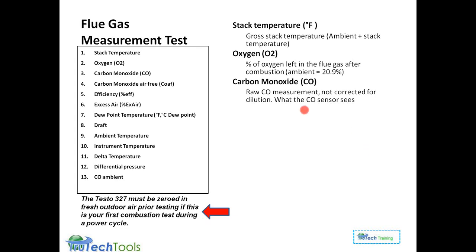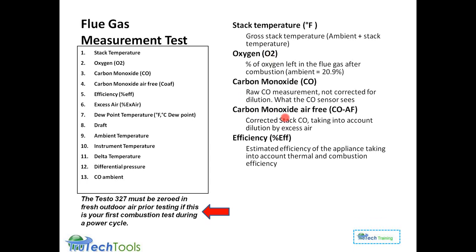The carbon monoxide is the raw measurement right from the CO sensor here. It's what the CO sensor sees. It's not corrected for dilution. CO air free takes into account the dilution by the excess air. It also uses the oxygen sensor that's present. Efficiency is the appliance efficiency that's taken into account. We talked before about how it's calculated. We get into a little bit more in depth.